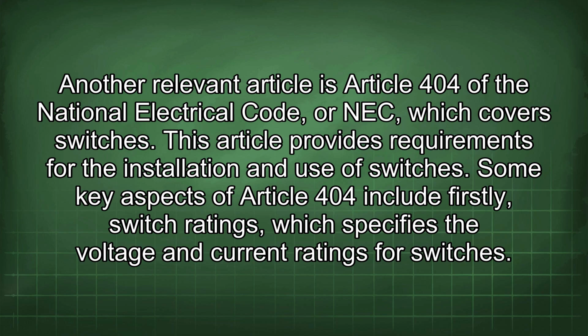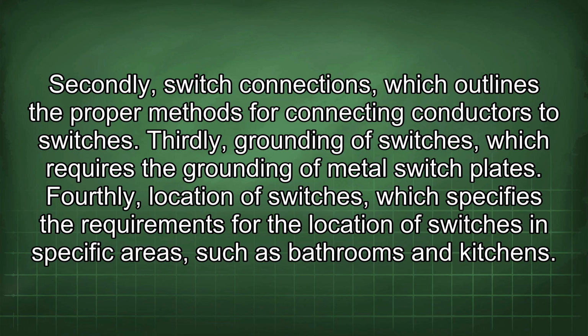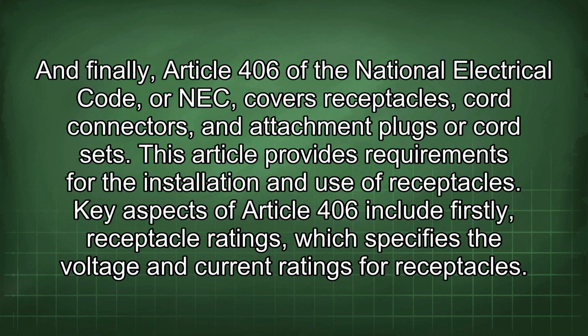Another relevant article is Article 404 of the National Electrical Code, or NEC, which covers switches. This article provides requirements for the installation and use of switches. Some key aspects of Article 404 include, firstly, switch ratings, which specifies the voltage and current ratings for switches. Secondly, switch connections, which outlines the proper methods for connecting conductors to switches. Thirdly, grounding of switches, which requires the grounding of metal switch plates. Fourthly, location of switches, which specifies the requirements for the location of switches in specific areas, such as bathrooms and kitchens.